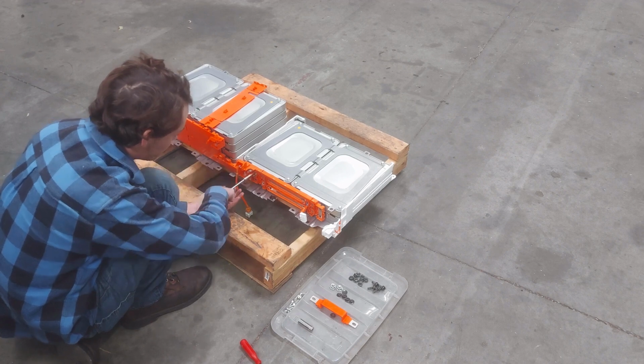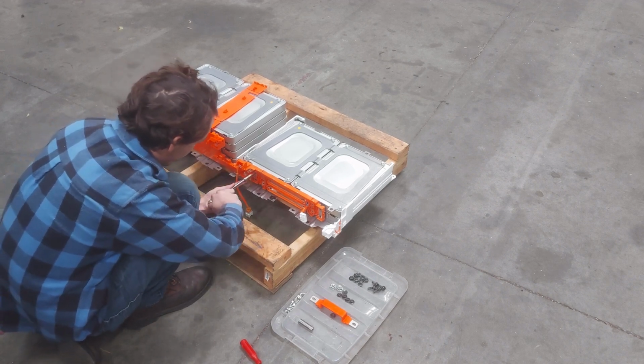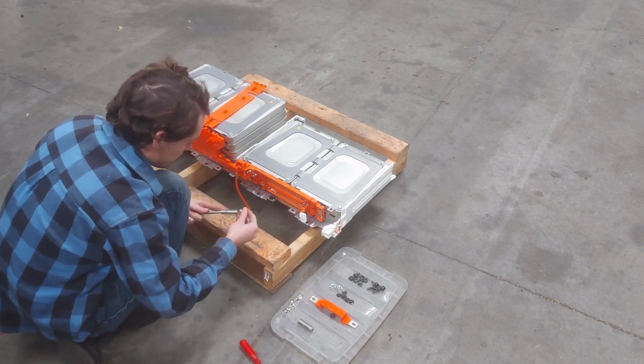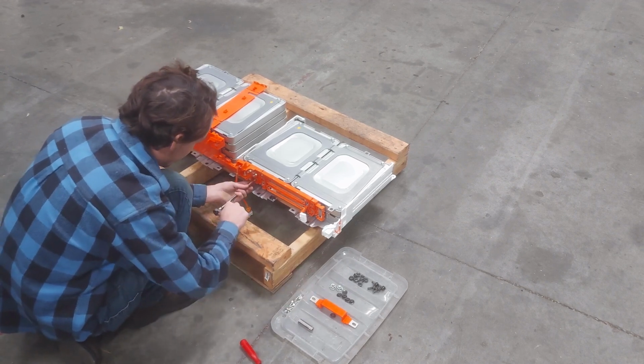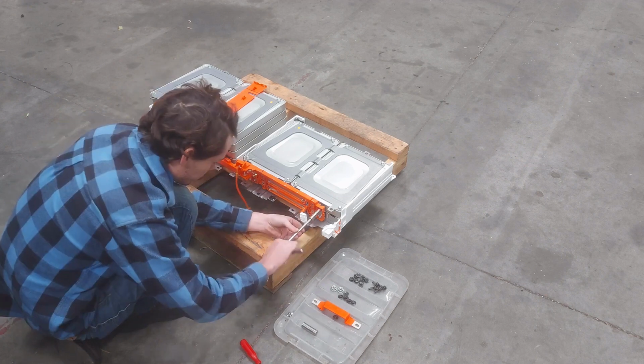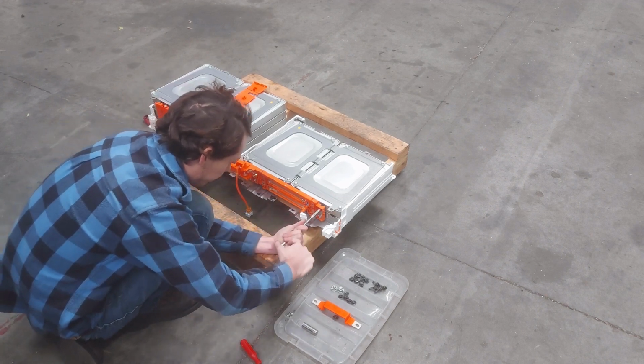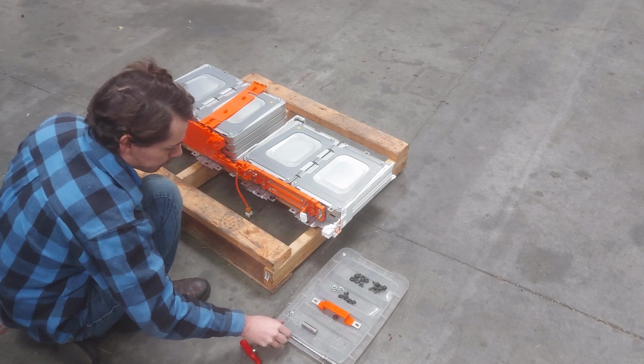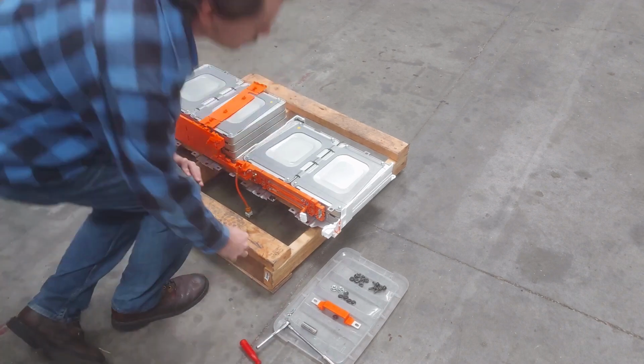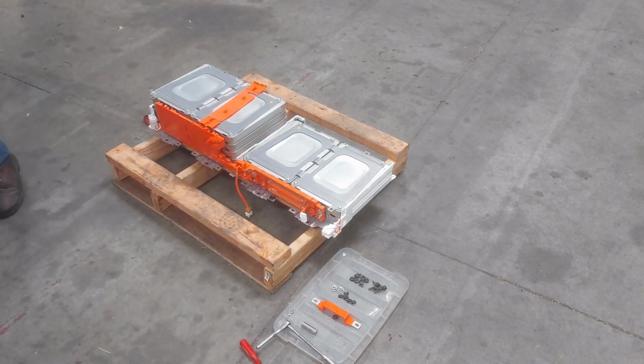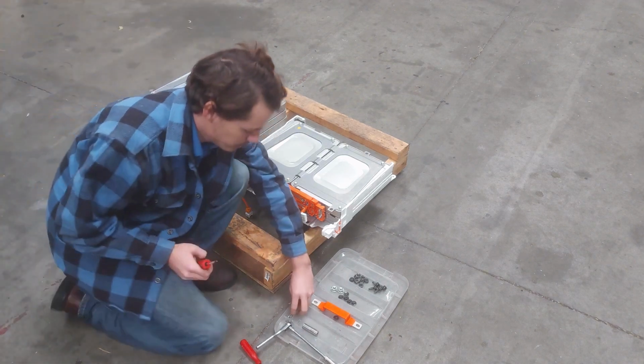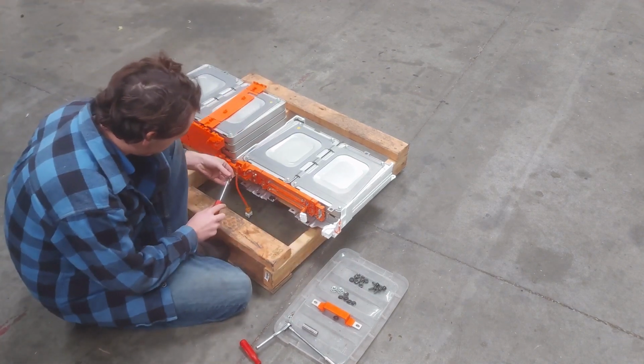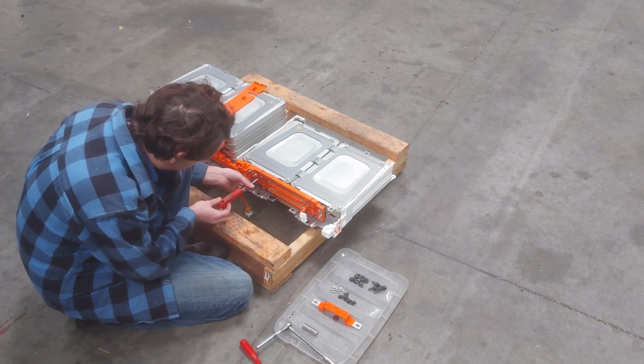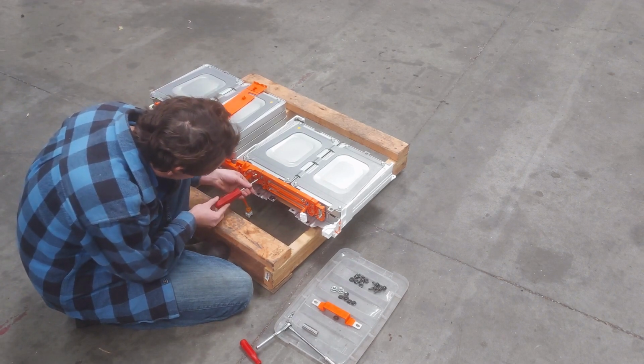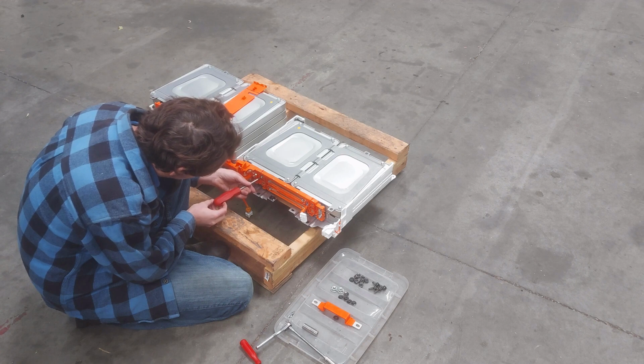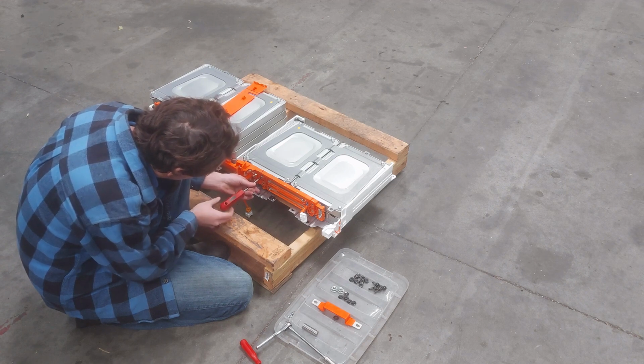I think the torque value on these is only about 49 inch-pounds, or about 4 foot-pounds, so it's not very much. Alright, and then we just have to put in the screws that go in the middle terminals. These are just solely so the BMS can monitor the voltages and do the balancing. They don't carry any real power.